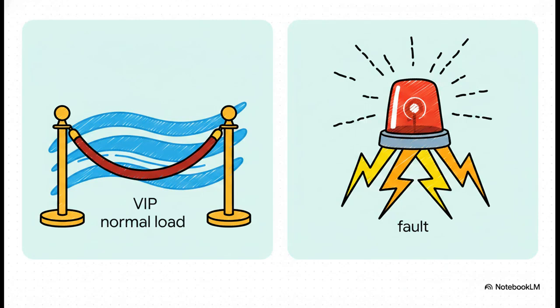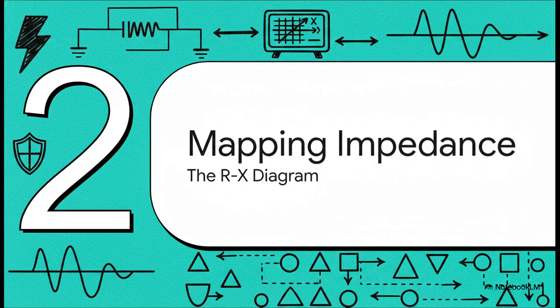And this brings us right to the central conflict of the whole system. Under normal, everyday conditions, your voltage is high and your current is steady. That combination creates a high impedance. This is our VIP guest, right? The normal load. But when a short circuit or a fault occurs, the voltage absolutely plummets and the current skyrockets. Suddenly, the math flips. The impedance drops massively. To the relay, this sudden, drastic drop is a giant flashing red light, signaling that a dangerous intruder is on the line. Section 2. Mapping impedance on RX.